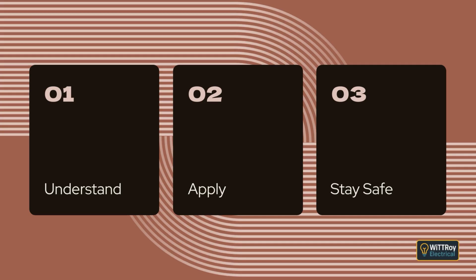Clause 7.5.2 Compliance with other sections. This clause explains that extra low voltage installations must be of either SELV or PELV systems. The particular requirements in this clause replace or modify other parts of the standard when needed. If no special requirement is given in this clause, the installation must follow the other sections. When an installation operates at extra low voltage but does not meet the rules for SELV or PELV, it is considered to be an installation operating at low voltage and must meet the requirements for low voltage systems.